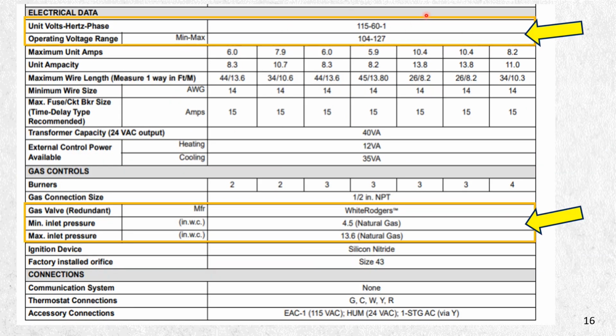Here's your volts. It's 115 volts. Imagine that. It is not 208 230. And anytime you put 208 230 on these furnaces, you're going to blow it up. So we have seen that happen. Some people try to do that and don't even read this. But you have to have a circuit of 104 to 127 volts on it. And then I was trying to see if we had our amp control. Yeah, right here, it's 35 volt amp.